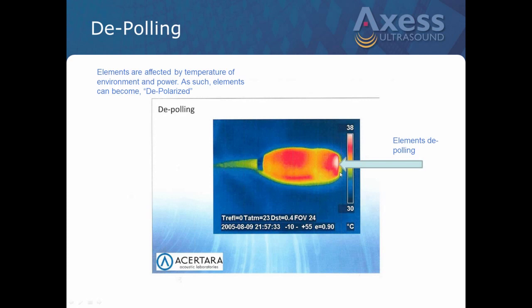Now here's an example showing an infrared view of a probe that has become depoled down here where the arrow is. This red here is electronics in the probe, that's okay, but this should not be this hot. Typically there should be some heat. Obviously ultrasound puts out some heat, but as you can see, this bright red shows the probe is depoling because there's too much heat being generated by the probe in some fashion or form. So again, it could be just that the environment it's in is too hot, or something with the transmit power applied to the probe, etc. But this is not a good thing right here.